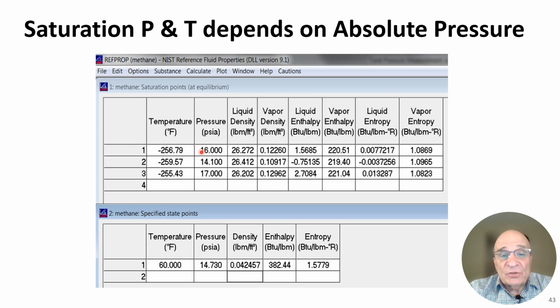So with that, I'm showing for 16 psi absolute, minus 256.79. Now, what happens if I increase that pressure? Well, if I increase the pressure, the temperature is going to get warmer. If the temperature gets warmer, what's going to happen to my density? My density is going to drop. Why will it drop? Because that liquid is going to expand.